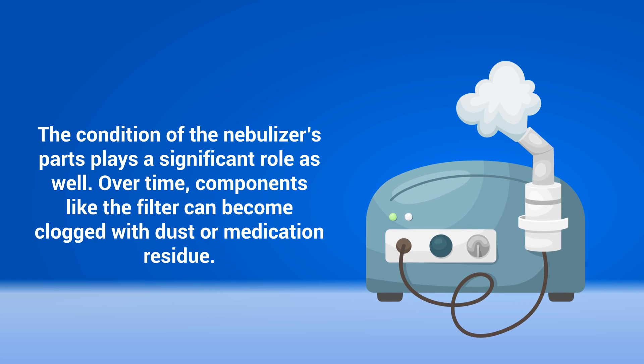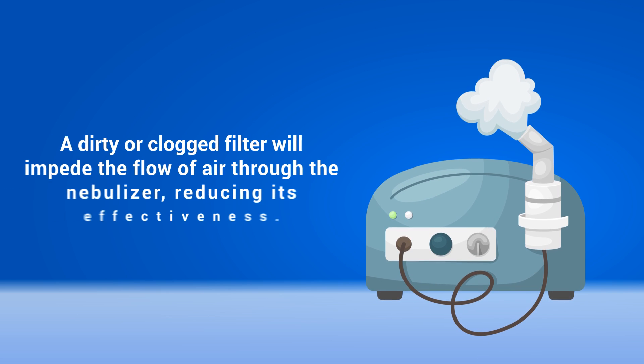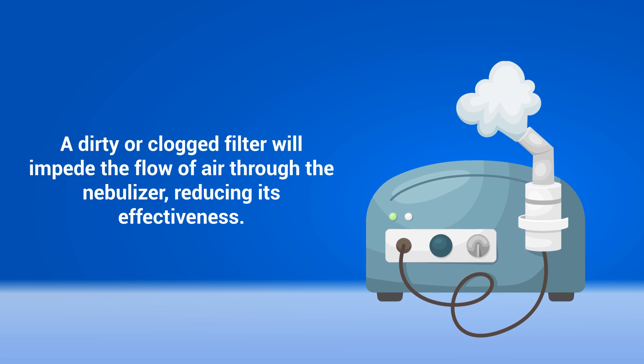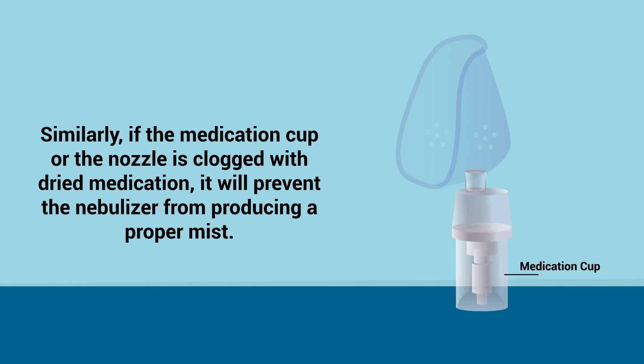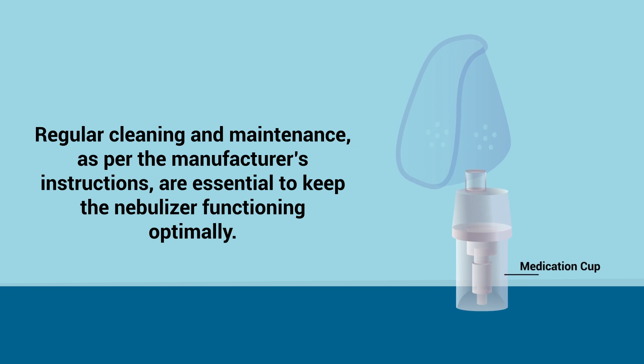The condition of the nebulizer's parts plays a significant role as well. Over time, components like the filter can become clogged with dust or medication residue. A dirty or clogged filter will impede the flow of air through the nebulizer, reducing its effectiveness. Similarly, if the medication cup or nozzle is clogged with dried medication, it will prevent the nebulizer from producing a proper mist.